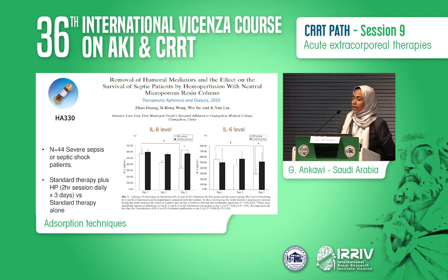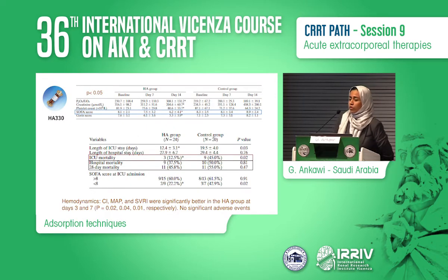Moving on to a different type of cartridge, but also in the context of sepsis. Here, the HA330 cartridges studied by a group from China. In septic patients, 44 patients, therapy is typically given 2 hours for 3 days. There was reduction in IL-6, IL-8, and there was improvement of hemodynamics. There's improvement of SOFA score, but not so much mortality.